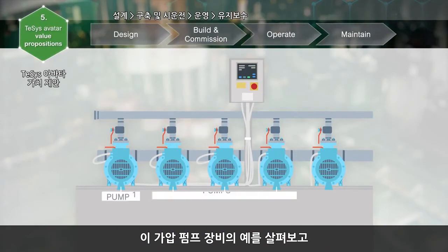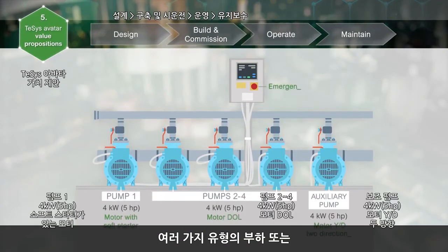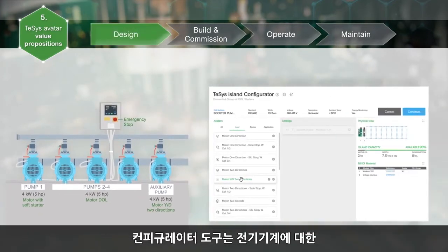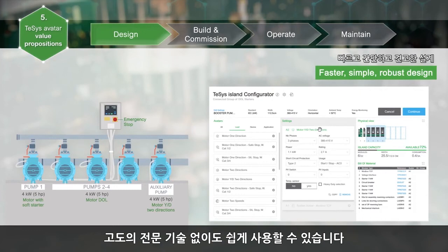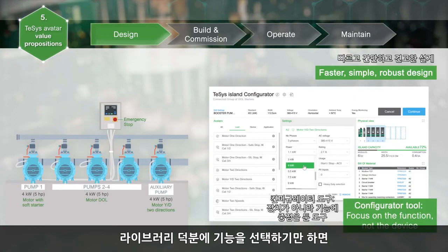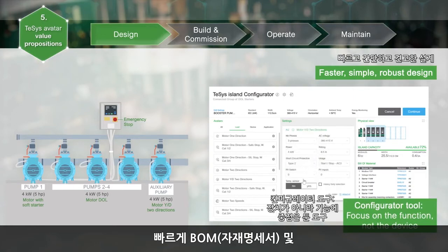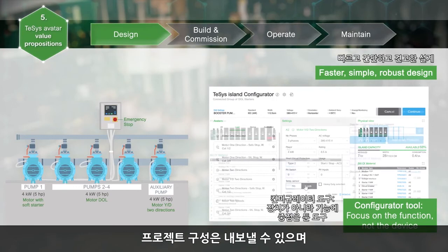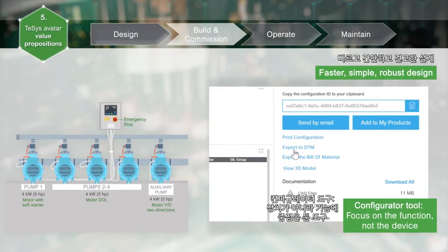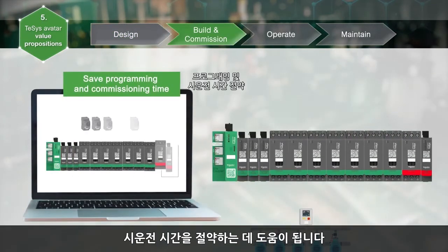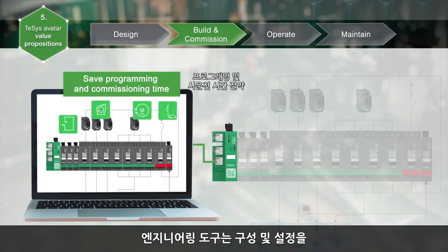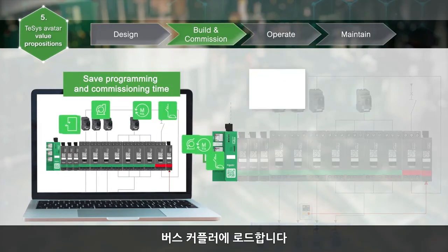Taking the example of a booster pumping machine and its different types of loads or devices: the configurator tool is easy to use without high electromechanical skills. The bill of materials and the topology are obtained quickly by selecting functions from the ready-to-use library of TeSys Avatars. The project configuration can be exported and then imported into the engineering tool, which loads the configuration and settings to the bus coupler, saving programming and commissioning time.